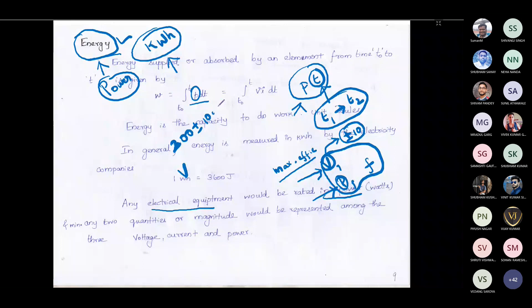This is the rated voltage. If a device is mentioned with a rated voltage, you should not operate beyond plus or minus 10% of the rated voltage. Your device is designed to operate effectively only for a certain voltage gap, you can say tolerance. So if your device is rated for 200 volt, let's say, then your device will work effectively for plus or minus 10% of this voltage. Generally they design like this, means that if you give maximum 220 volt, it will work effectively, and minimum 180 volt, it will work effectively. Within this range only it is going to work properly. That's why they are mentioning this tolerance.